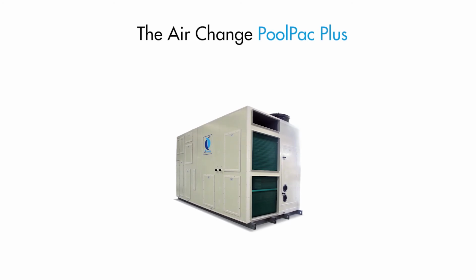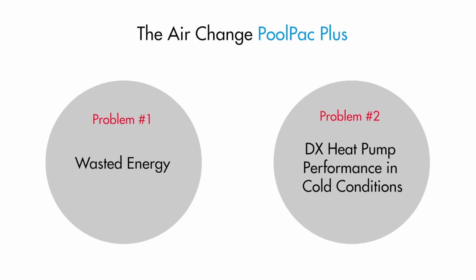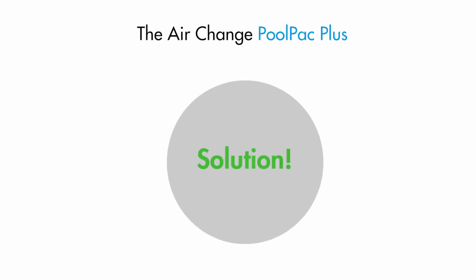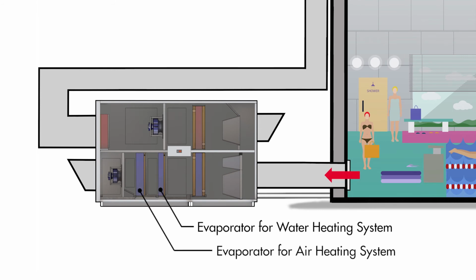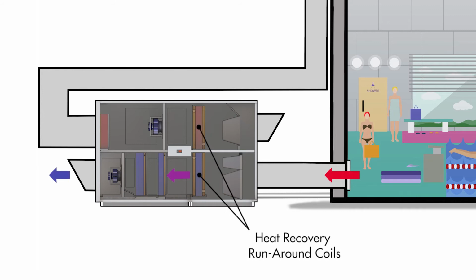So how can the Air Change PoolPac Plus solve these problems? Essentially, the PoolPac Plus addresses problems 1 and 2 by, well, combining them. With the PoolPac Plus, the evaporator coils of the DX heat pumps for the pool water heating and the air heating are placed in the exhaust air, downstream from the heat exchanger. This means that any surplus energy that remains in the exhaust air after the heat recovery system is absorbed by the DX heat pump to improve its efficiency.